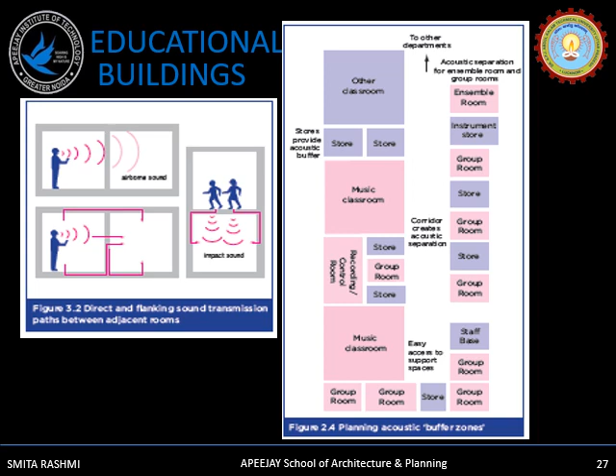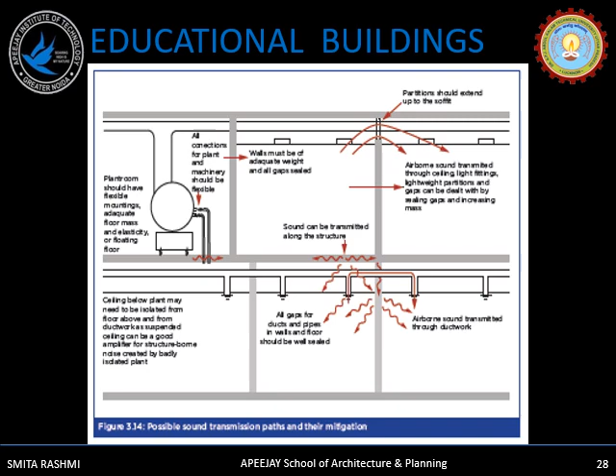Plant rooms should be mounted on vibration absorbers to dampen the noise, or mounted on a floating floor. All connections to the plant should be flexible. The mass of the walls should be adequate and all gaps should be sealed. Acoustical seals can also be provided at door openings. If the partition stops below the false ceiling, airborne sound can be transmitted through ceiling light fittings, so the partition should be taken up to the soffit of the ceiling level. Airborne sound can also be transmitted through ductwork, so all gaps between ducts and pipes should be well sealed.